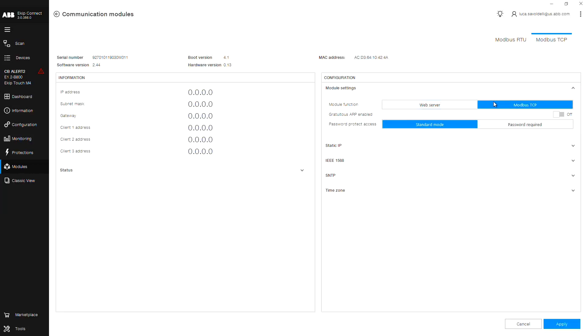The second is Modbus TCP, which is for the standard Modbus TCP communication to a supervisional or SCADA system and allows for both reading and writing. Please note, writing is only available when the circuit breaker is in remote mode.